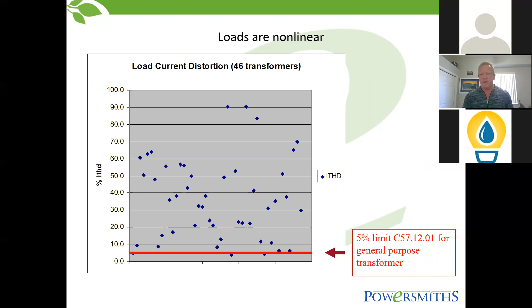Then the next thing is heating. Especially in Texas, I'd say the majority of electrical rooms you see are cooled, and the only reason they're cooled is because of the heat generated from the transformer. So now you've got a transformer sitting in an electrical room being cooled by the chiller, and you're cooling heat that shouldn't be there in the first place. So now you've got more energy consumption.